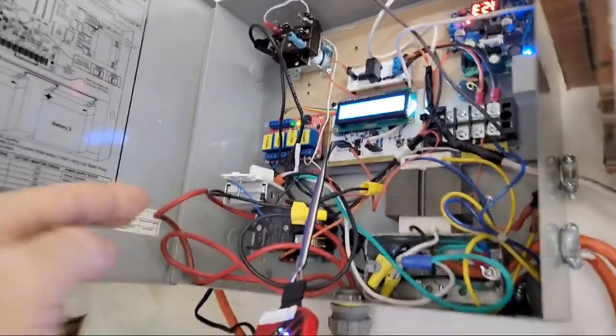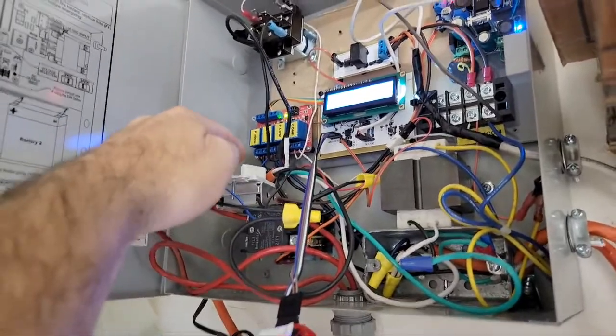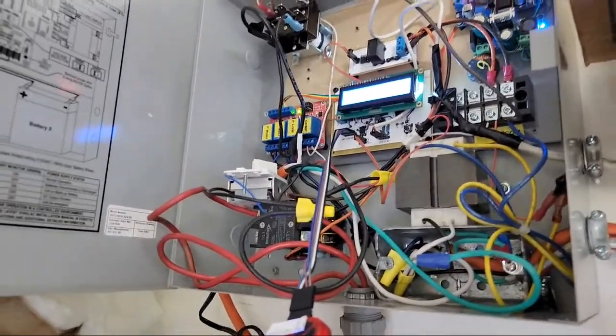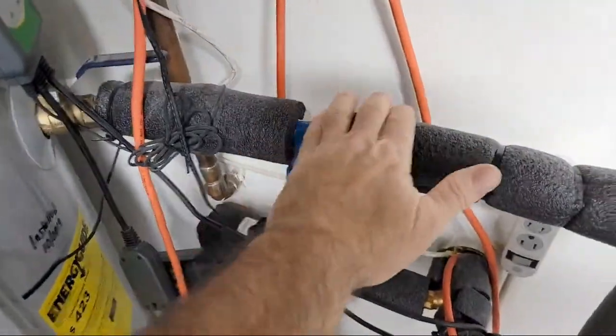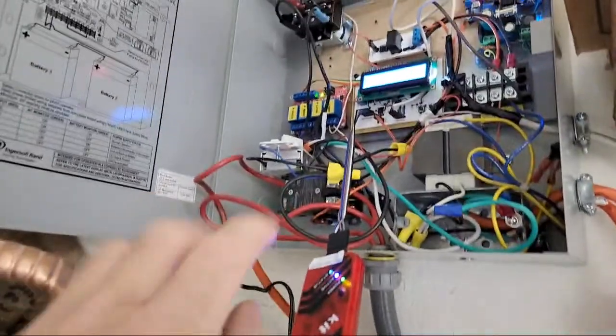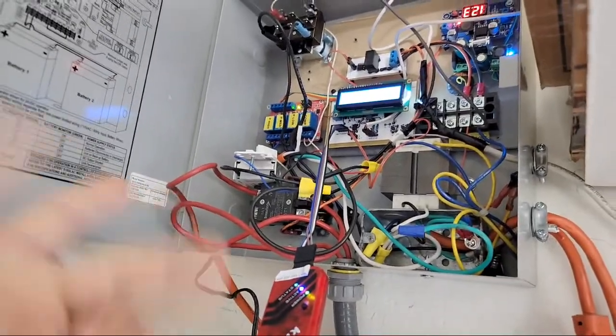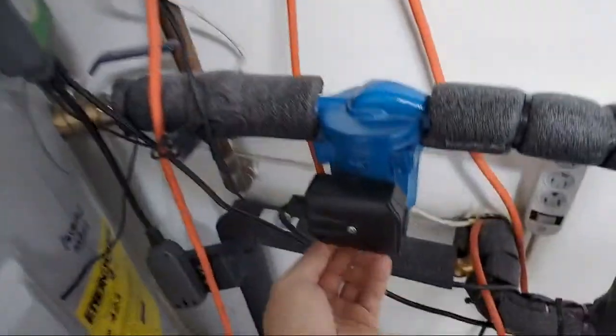And then I'm using 2 relay outputs. One is just simply going through this little light dimmer, using it for the triac control, like a wave clipper, just to slow down the pump. And then the second relay just bypasses that basically, and then the motor goes to the full set speed on the pump.